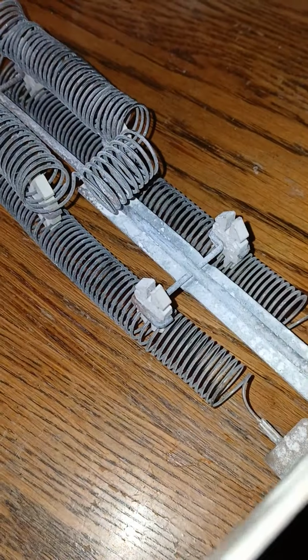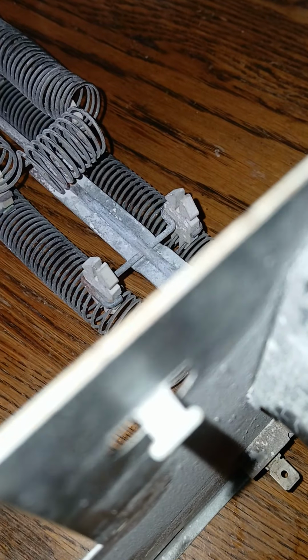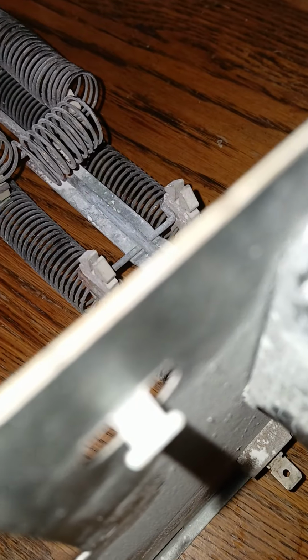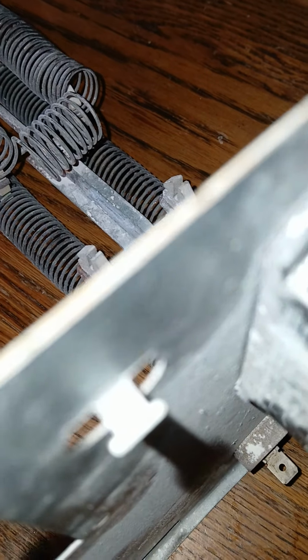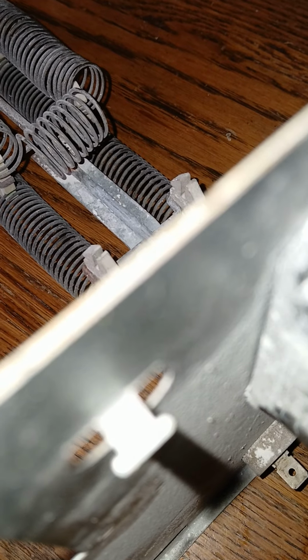These are heat strips for a heat pump. These are a 5K. Again, they're different sizes. One needs to size the wire and the breaker according to the size. 5K means 5 kilowatts. This is used for a heat pump, not a gas furnace. Again, heat strips for a heat pump, not a gas furnace.